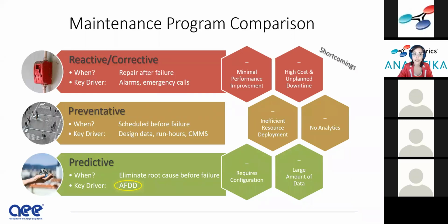You're putting a Band-Aid on it, you're replacing it under unideal conditions, meaning you're usually rushed with an unplanned stop. The key drivers here are actual BAS alarms, hot and cold calls from people, actual visual inspection that something has broken or a valve has started to leak or whatnot. But you're really limited to alarms and hot and cold calls, and then just failure. A coil is frozen in the winter, and that happens. And so we're trying to avoid those sort of things.